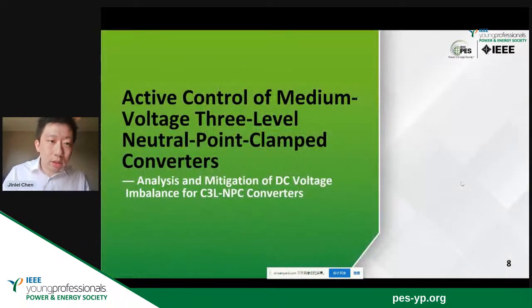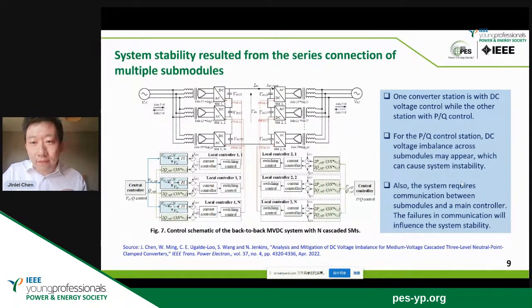Based on this testbed, I conducted the stability-related DC voltage balance control. For this type of converter, one converter station is with DC voltage control, while the other station is with power control. For the power control side, the DC voltage imbalance may occur due to the cascaded topology. This will influence the system stability. Also, the system requires communication between the submodules and the main controller. Upon loss of the communication, the system will also face instability.